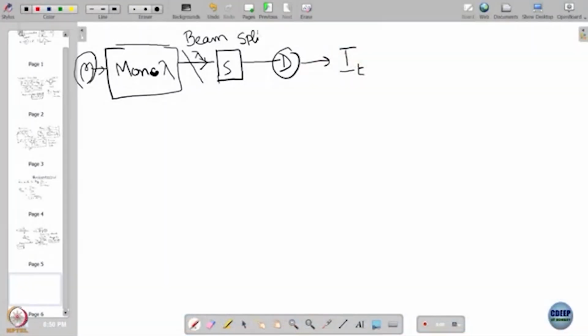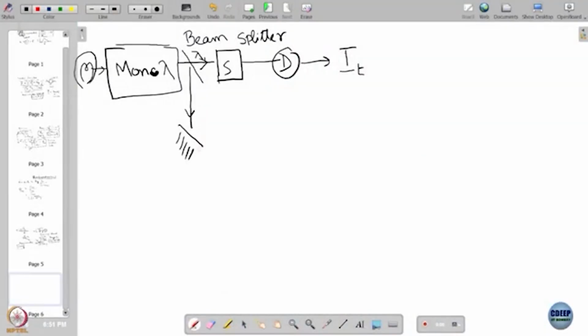But the split beam spectrophotometer is much more common, sometimes called a dual beam spectrophotometer. What you do is you put in a beam splitter. You can think of a beam splitter as a partially reflecting mirror. Typically, in absorption spectrophotometers, you want to use a mirror with 50% reflectivity. 50% of light goes through, 50% is reflected, and nothing is absorbed. So, I0 will be IT in this direction plus IR, the reflected part, but that IT will actually be I0 for the sample. So, it goes here, and then you have a completely reflecting mirror.